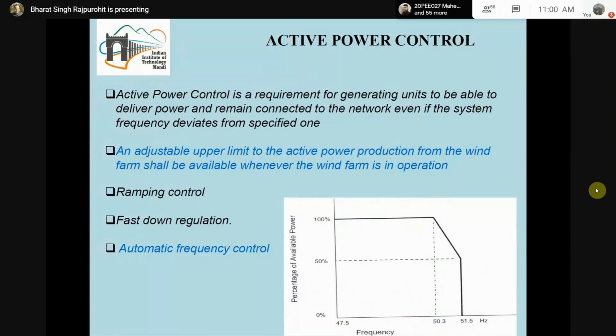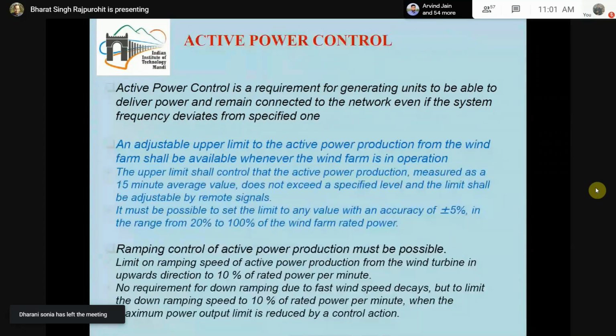This is from the Indian grid code. This curve expects that once the frequency is beyond 50 hertz, the output of the wind farm should be reduced, in a certain ramp, as shown here. And still, if beyond 51.5, the wind farm should reduce its output power to a zero value to maintain the frequency of the system. So this is what active power control is.